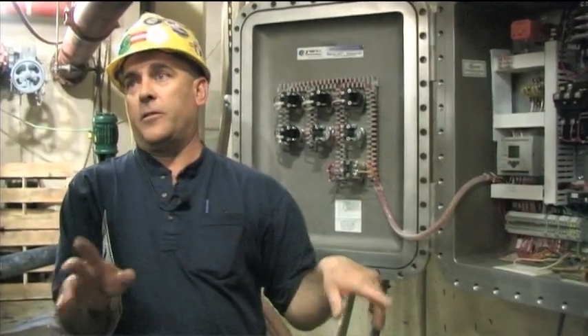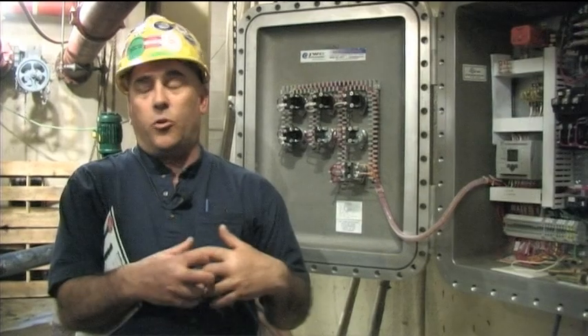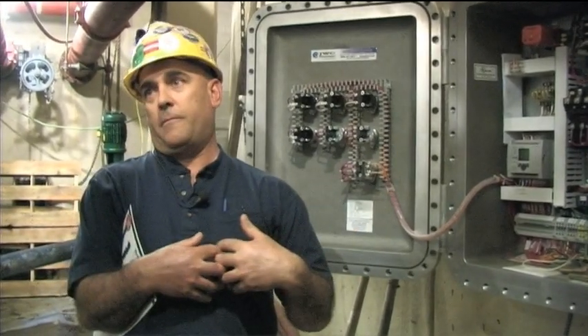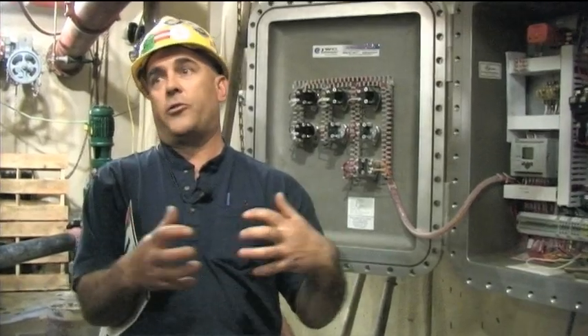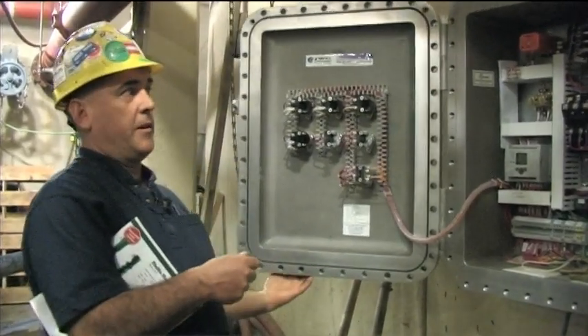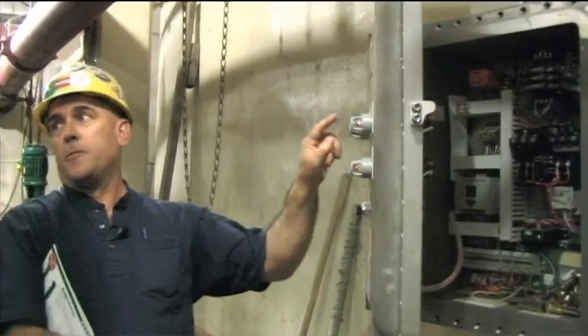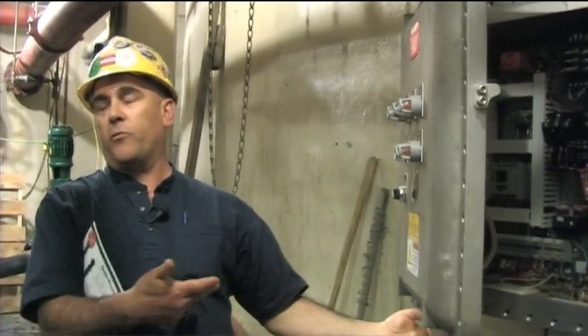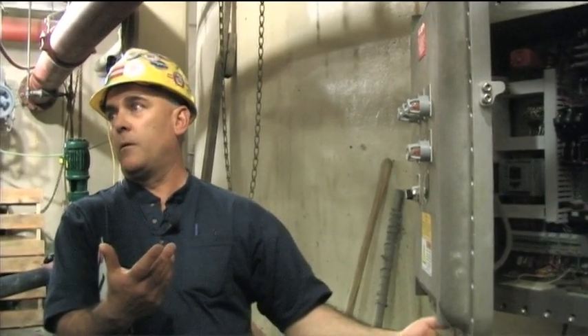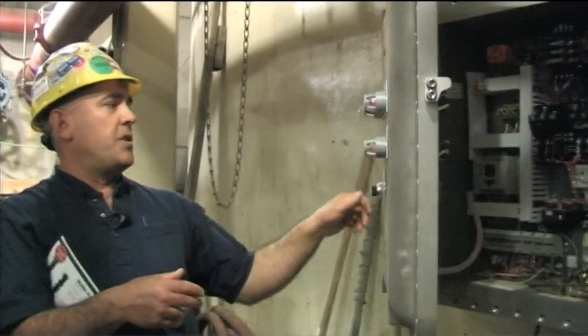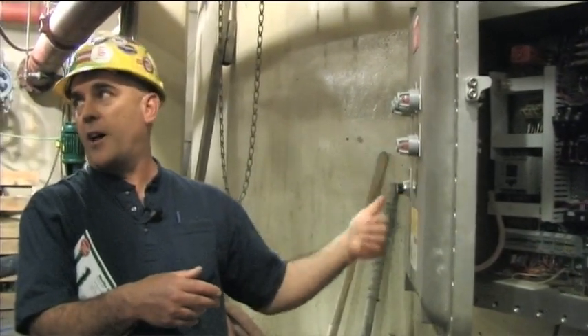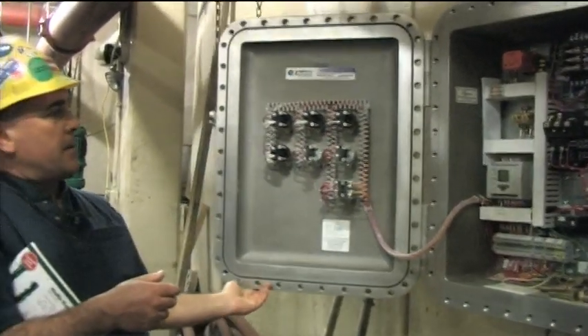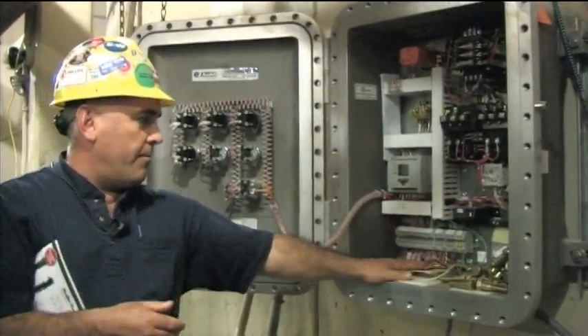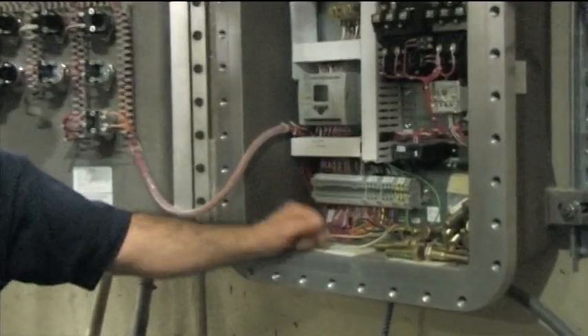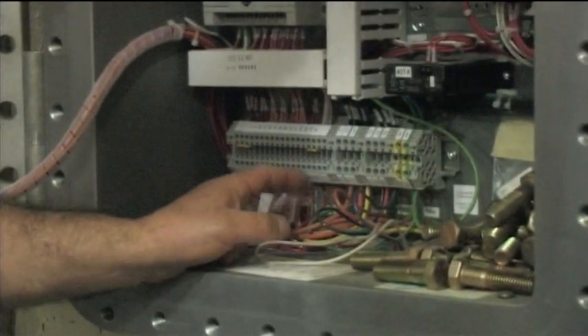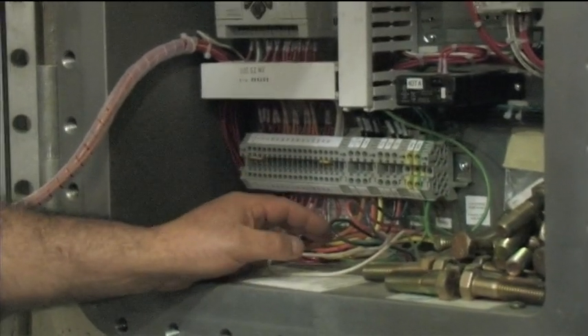So if it passes it, it just continues to run. If it still jams, it will reverse 3 times and try to pass that object. On the 3rd try, if it doesn't pass it, it's gonna trip and it's gonna tell you have a jam indication out here. This light will be flashing such that if you read the electrical drawing, it'll tell you that you have a jam. When that happens, you just have to shut the unit off, reset it, and then start it. And then down here is just your terminal strip with your wiring going out to the motor, any wires going to SCADA for control, and that's about it.